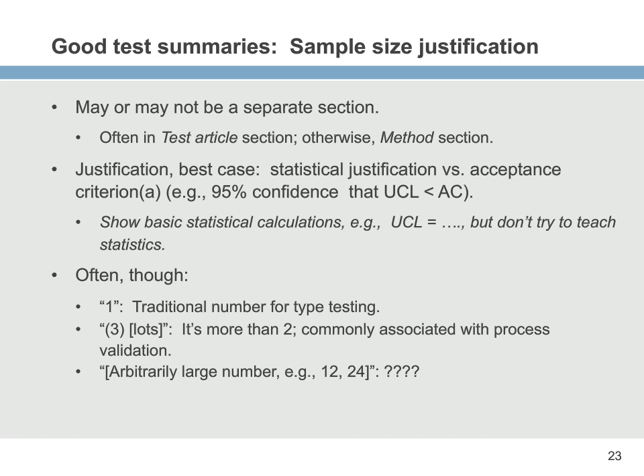It's good to show, as I said, statistical justification, but don't try to teach them statistics. One of the difficult things about sample size justification that FDA likes to push on is there's sometimes a misunderstanding, especially with young reviewers. A lot of medical device testing is just one. It's type testing. It's assumed that if you can test the one and it passes, that repeatability is just not going to be an issue. So you have to say, hey, we chose one because that's typical for this, and it's okay by the standard. Sometimes it's 3 or 3 lots.